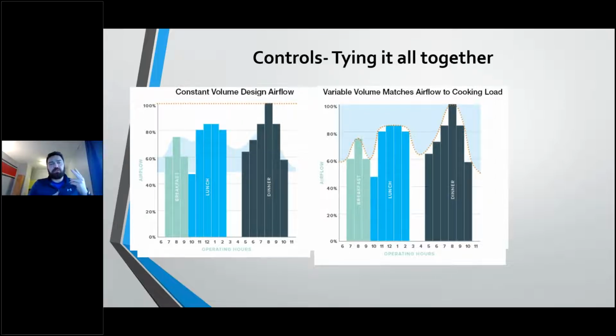Now I mentioned that there are two different control types in the market. There's a constant volume control type, and then there's a variable volume control type. Constant volume is exactly what it sounds like. We're going to hit our minimum temperature set point, which in most instances is somewhere around 90 degrees Fahrenheit. Once we've hit that minimum temperature set point, we're just going to run these fans at 100% of design, regardless of the cooking application that's happening underneath that hood.